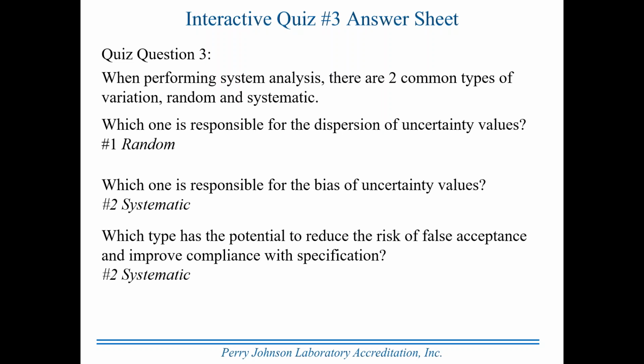And it's systematic because if you correct or adjust the bias, you will bring the results closer to being within specification. In fact, in the example we looked at, it came completely within specification by reducing the bias. Laboratories can choose, if their equipment is within specification but has a rather large bias, they can still use it. It's still within specification, still satisfies the 95% requirement in that regard. Most laboratories, though, want to adjust it back as close to mean as possible, and that improves even more the extent to which it's within spec, which means that it can tolerate some displacement.